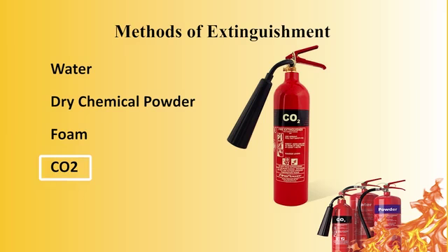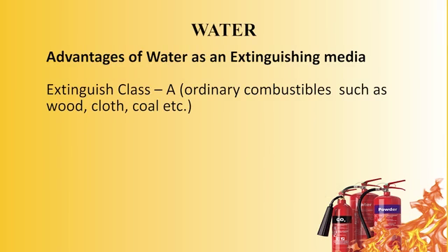Now the properties of water as an extinguishing media. Why water? Smothering, by reducing oxygen percentage, water extinguishes the fire. By cooling, by reducing down the temperature, water extinguishes the fire. These are the advantages of water as an extinguishing media. It can extinguish Class A fire, the ordinary combustibles such as wood, cloth and coal.